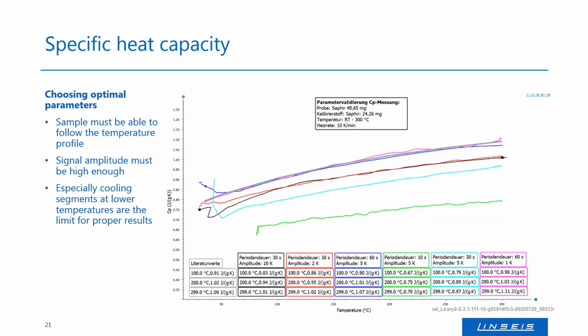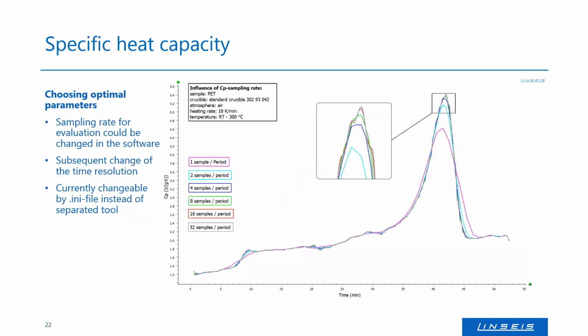And that's it here. So this is normally my recommendation. We use mostly in the first try a 60 seconds period and an amplitude of 1 Kelvin at a 10 Kelvin heating rate, and mostly also at 5. So this is a good setting. What's also important is the sampling interval for our amplitudes. There are some different options we have in our software. Of course, you can also just smooth the result, but you can also choose a different sampling interval directly in the file system of our software.